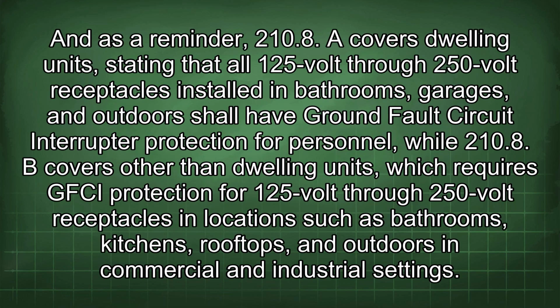And as a reminder, 210.8 A covers dwelling units, stating that all 125 volt through 250 volt receptacles installed in bathrooms, garages, and outdoors shall have ground fault circuit interrupter protection for personnel, while 210.8 B covers other than dwelling units, which requires GFCI protection for 125 volt through 250 volt receptacles in locations such as bathrooms, kitchens, rooftops, and outdoors in commercial and industrial settings.